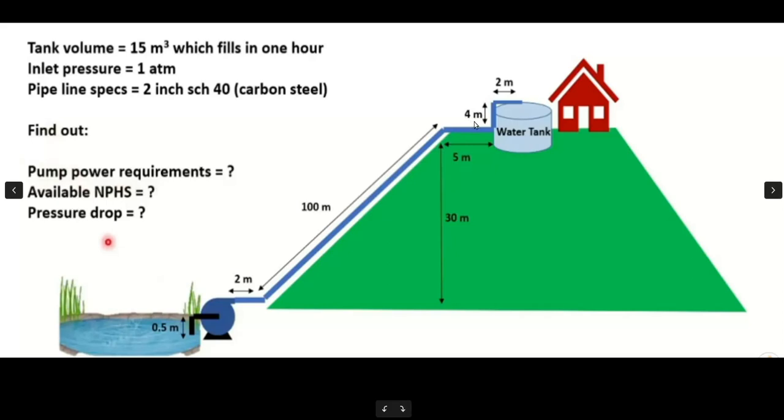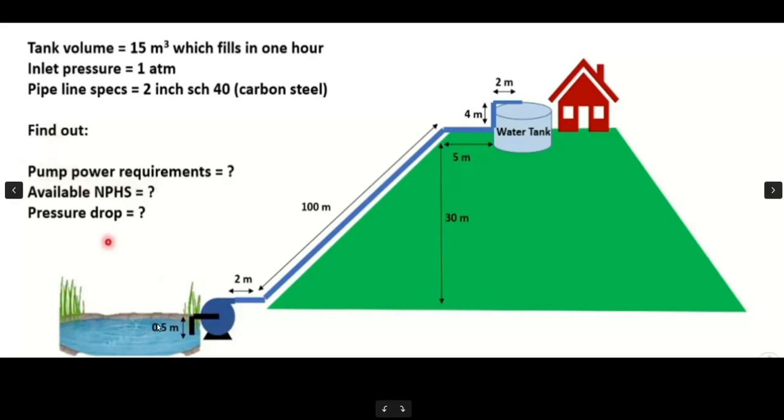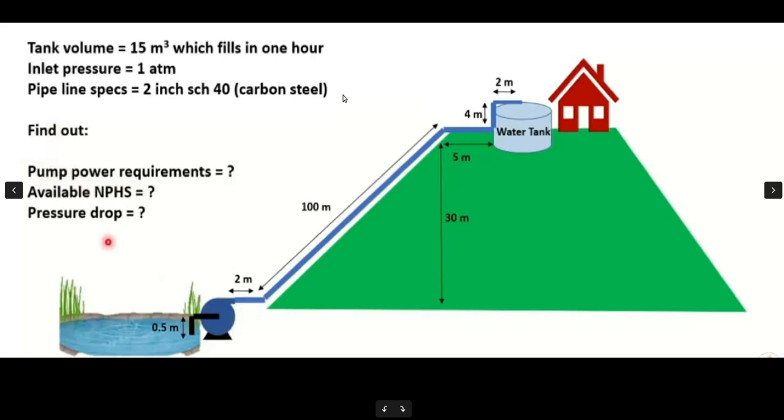Hi! I'm going to dimension this pump to see how much power I'm going to use to pump from 0.5 meters below the pump and up to this tank here. The tank is 15 cubic meters and it has to be filled in one hour and the inlet pressure here is one atmosphere and the pipe is two inch and made of carbon steel. So let's do it.